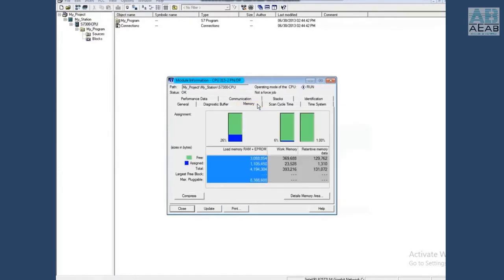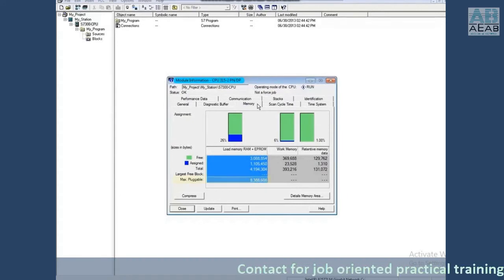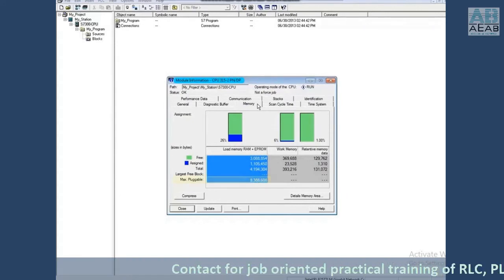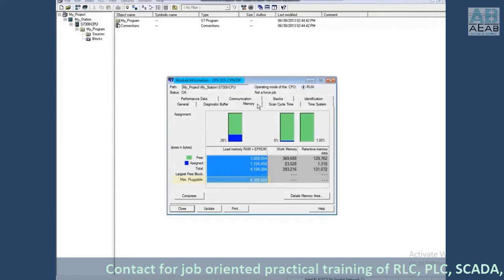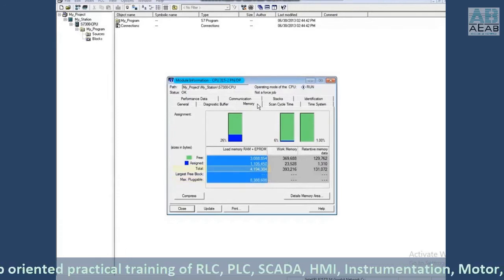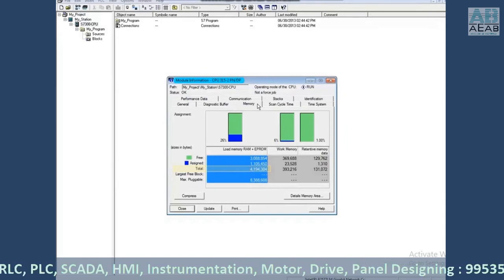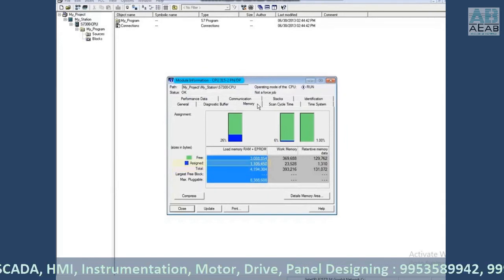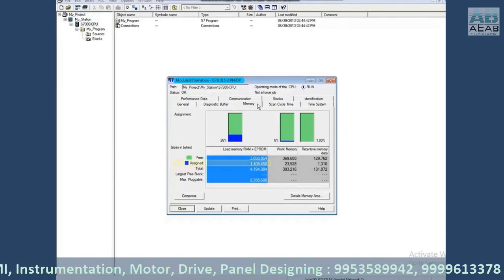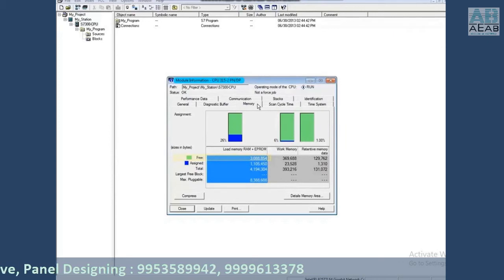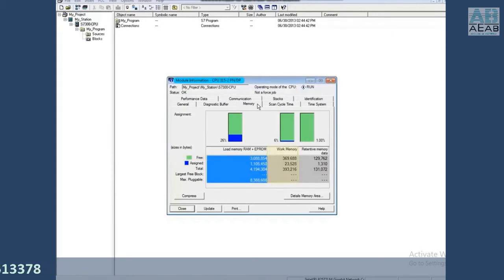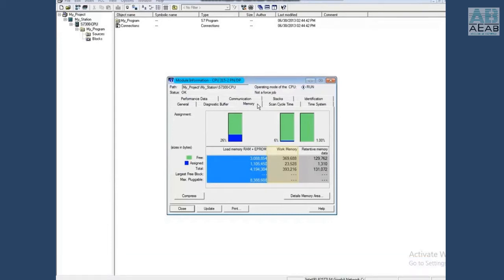In the case of the S7-300, the CPU's RAM or load memory is the micro memory card (MMC). The max MMC that this CPU can take is 8 megabytes; the size of the actual MMC is 4 megabytes. The amount of memory in use is 1 megabyte, and the free memory is 3 megabytes. The work or high-speed memory is 393K. The retentive memory that retains data through a stop and run cycle of the CPU is 131K.